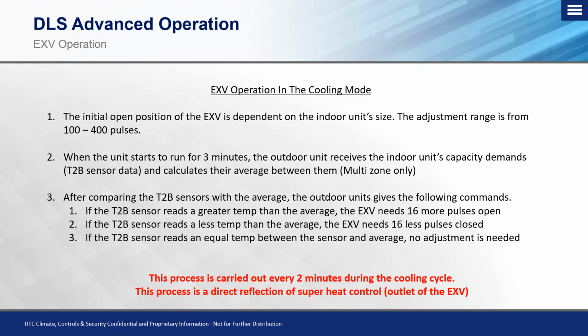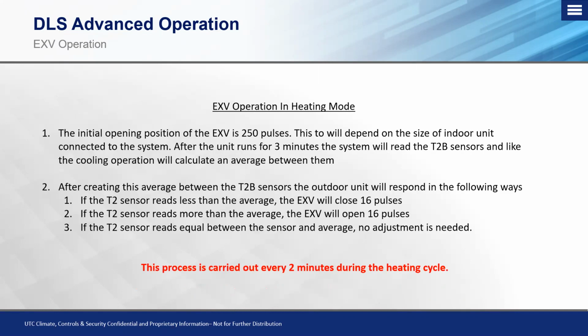Okay, so in the cooling mode, we know when the sensor of that T2B reads greater than the average, we need to open up that EXV and allow more refrigerant to go into the indoor unit to cool that coil down. The T2B sensor, if it reads less temp than average, we know that there's too much refrigerant going to the indoor unit, so we need to close at 16 pulses, and they always move in those incremental 16 pulses open, 16 pulses closed. Okay, so that's cooling mode operation. So now we get into the heating mode operation with the EXV. Okay, so that initial opening position of the EXV is 250 pulses in the heating mode. This too will depend on the size of the indoor unit that is connected to the system, so it varies based on tonnage.